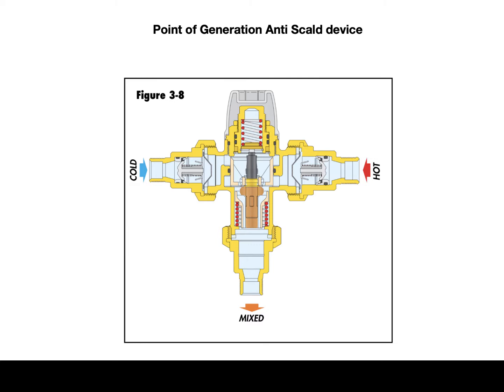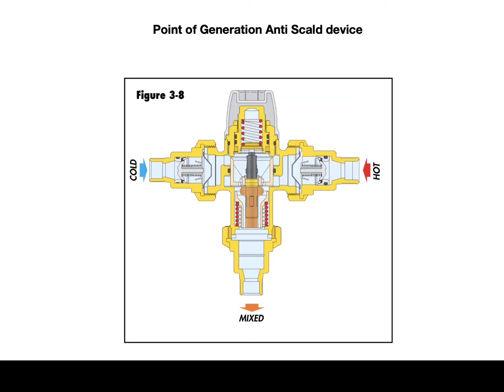This is a cutaway image of the point of generation anti-scald device. This device is designed so that if the thermal sensing element fails on the inside of the valve itself, it is guaranteed to close the hot water port off and allow only cold water to go through the mixing station itself. This is done to avoid the possibility of a scald situation occurring in the event of a thermal element failure, which is a very common failure. This valve must be in compliance with the ASSE standards for point of generation domestic hot water heating systems.